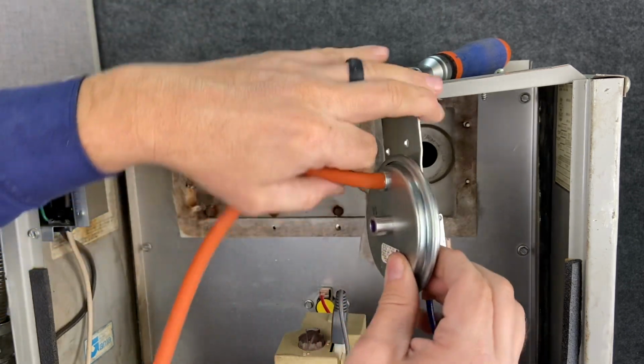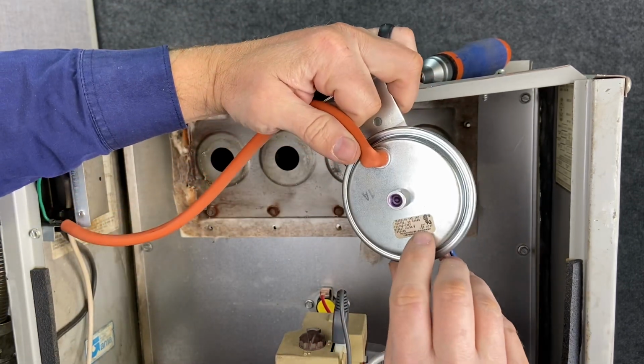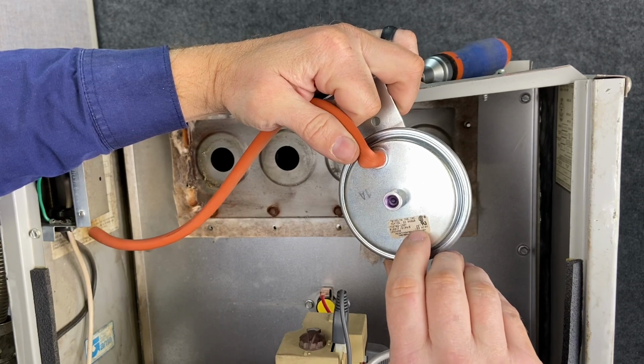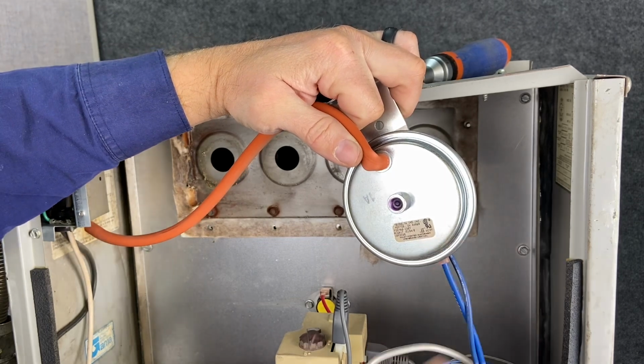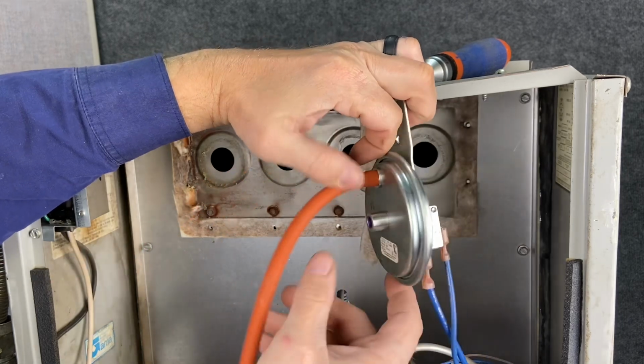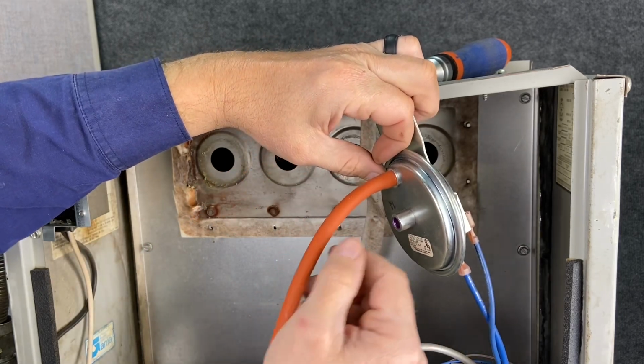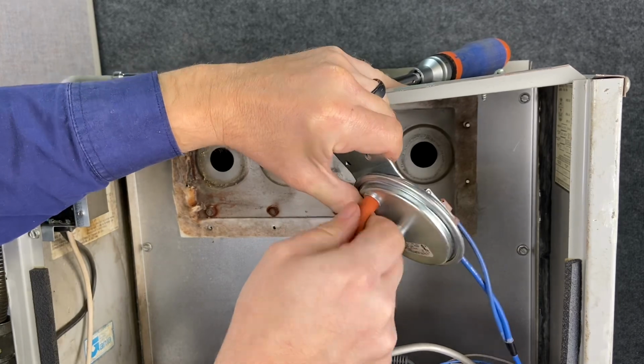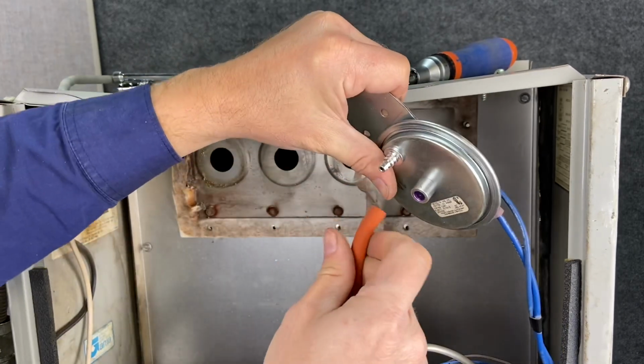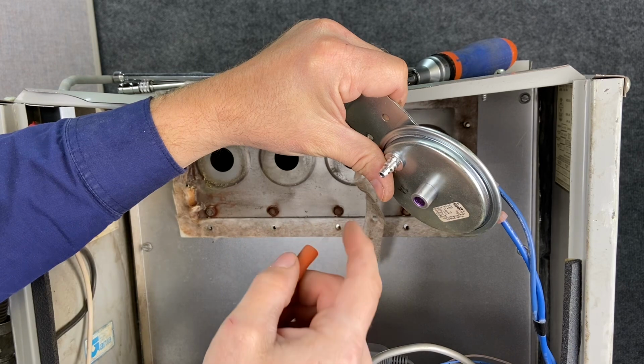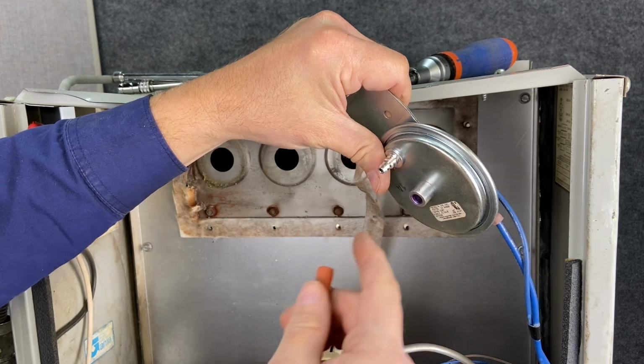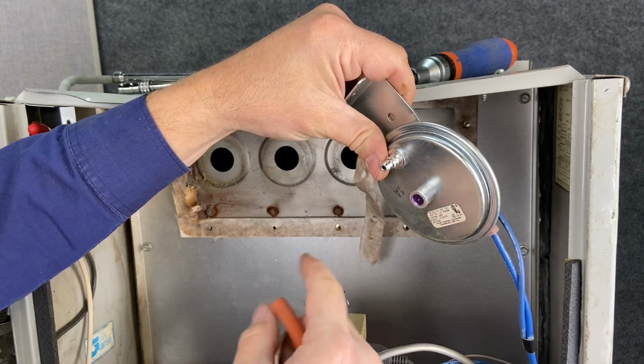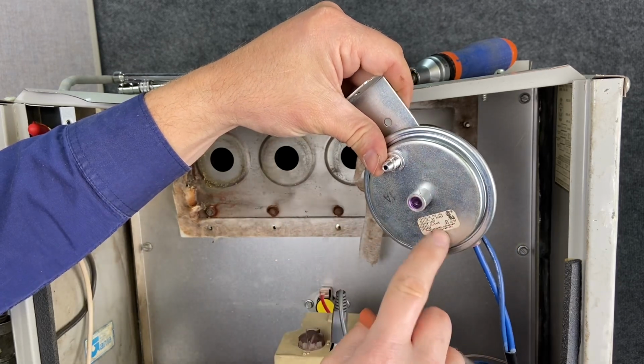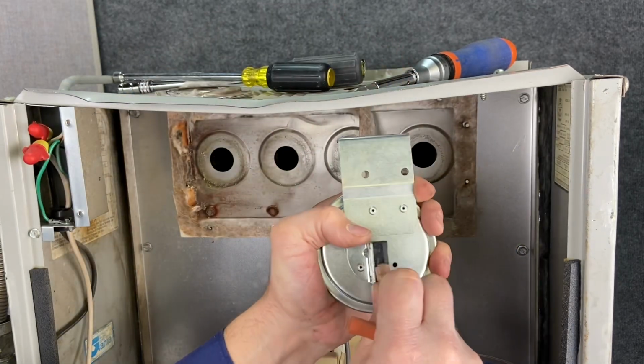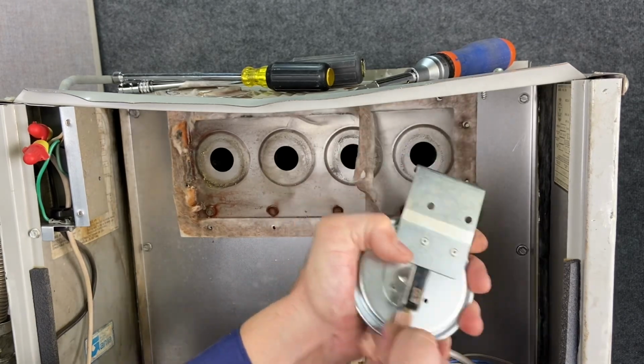We know it's working. These are all for different size pressures. If I read on this one, it's 0.65 inches water column pressure factor. So it's a negative pressure. So what we'd actually do is we could put a T in this hose or unplug the hose itself entirely. But notice this one's stuck really good. It's been there a long time. And I have a T adapter that I put here and to a magnehelic to this component. And as that inducer fan motor runs, I can check to see if I'm getting enough vacuum for the switch to close. It's a very simple component, just simply 2 wires, 1 hose, and 2 screws.